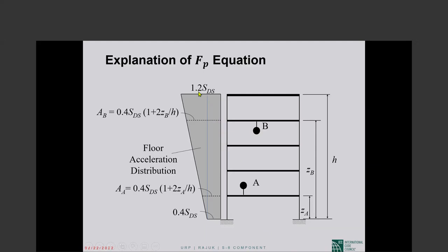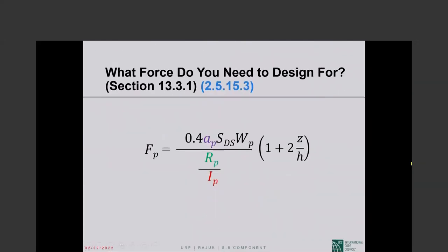At the roof level, we are considering 3 times as much acceleration, and in between it is a linear variation, and that is what is expressed by this expression. So for equipment, piece of equipment A, which is mounted at a height of Z sub A above the ground level, the component design force is equal to that, Z sub A over H. And for equipment B, which is mounted at Z sub B above ground level, this is the component design force, 1 plus 2 Z sub B by H. It's linear variation in between the base and the roof.